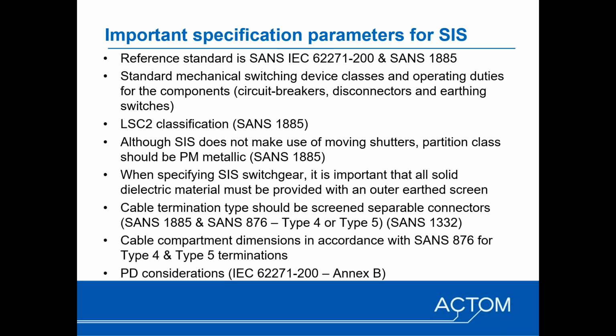Then cable compartment dimensions. So dimensions required to accommodate, for example, 3-core cables, which are commonly used in South Africa, certainly at 11 and 22 kV. It's important again to ensure compliance with SANS 876, which, for example, specifies for a 3-core cable that you need to provide 800 millimeters from the cable support clamp or the gland plate, whichever is higher, and the terminal fixing point on the bushings or the copper tags, depending on the type of connection you're making.